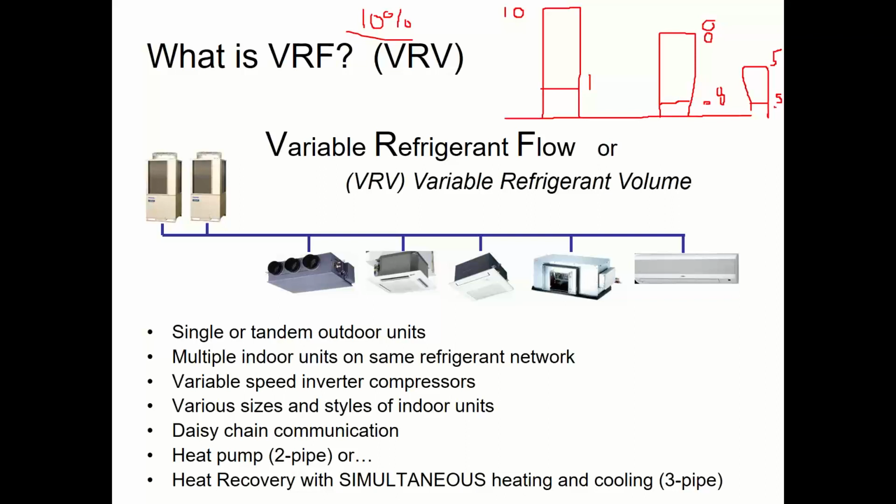And if I say let's double it to get all the heating done with the heat pump, now I can only go down to 1 ton instead of a half a ton. So where this becomes a problem is on jobs that have lots of zones. If I only got 5 zones, this oversizing thing is probably fine. But if I got 40 zones, and some of these zones are like 5,000 BTUs, 9,000 BTUs, little tiny things, and I can't get down to their capacity needs, then it starts becoming an issue.